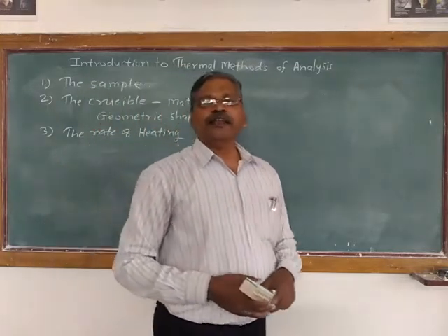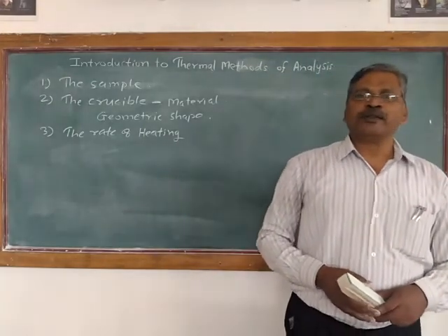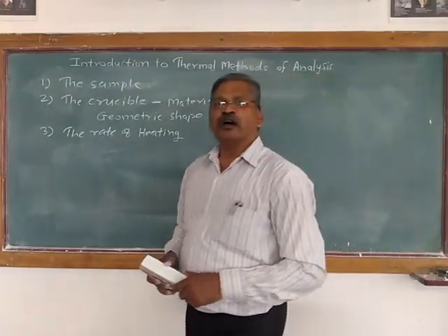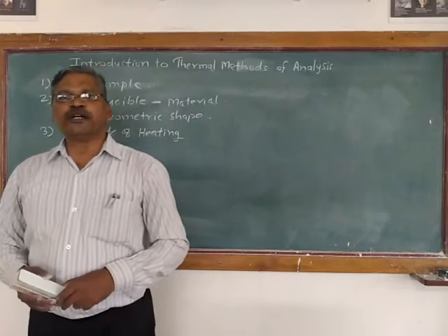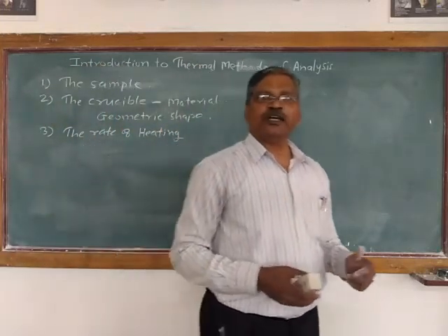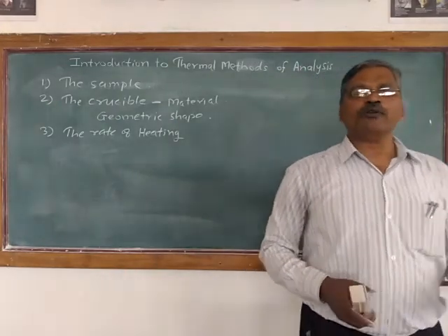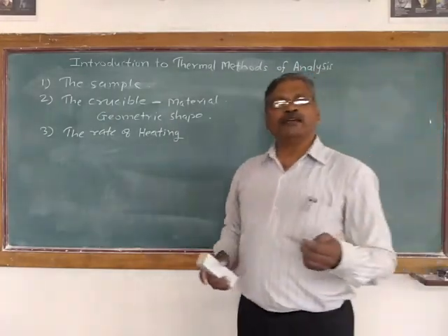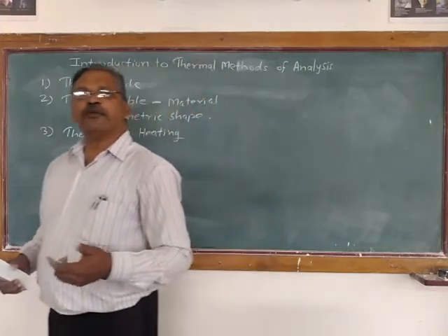Heating rates need not be linear and may follow a complex pattern which must be specified in detail. It is not necessary to keep the same heating rate throughout the experiment; it may change from the start to the end of the experiment.